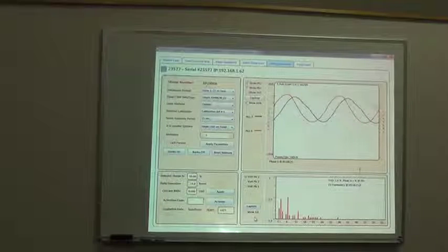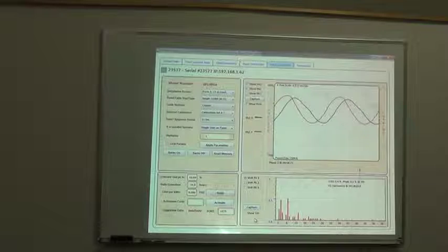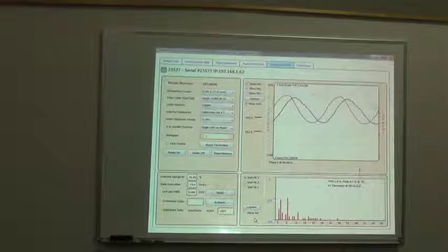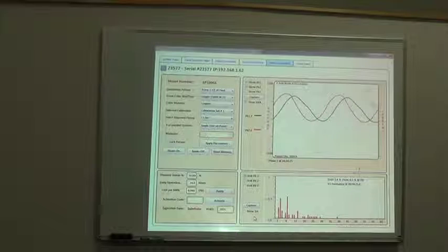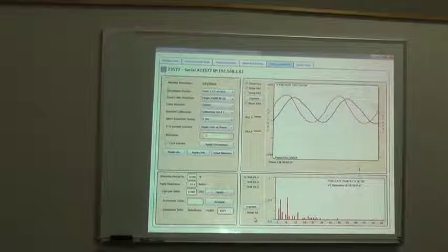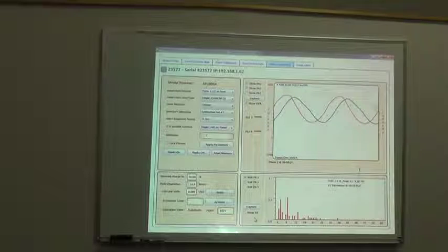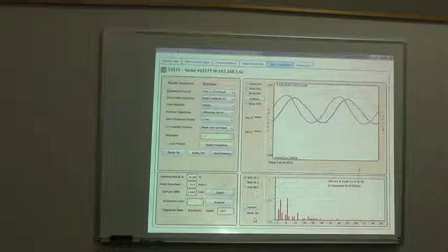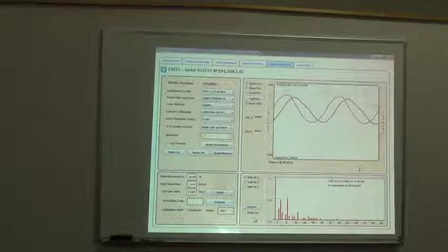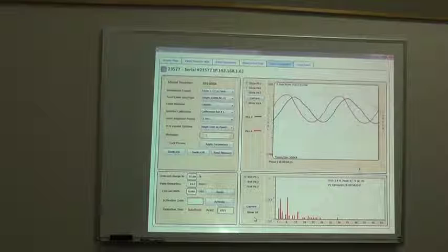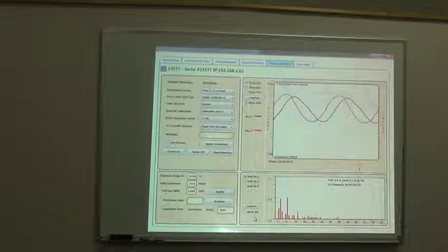Last week, we did an installation about a month and a half ago, and last week we got the first bill, and that one had a 14% saving. But the Fluke meter that we put in there with the data was showing about 14% savings. So that was great, that we got the exact same number that the Fluke 1730 was showing. So now I actually have a physical bill with the physical data that we took for 1 hour, and they match perfectly. I think it's a coincidence. That's too good, to be honest with you. I'll be happy with being within 30%. You know what I'm saying? It just happened to be the same number.